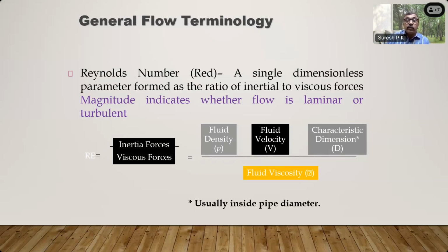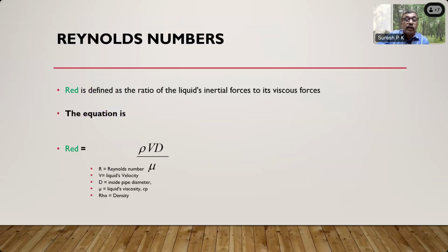So that is the Reynolds number. It uses the liquid's viscosity in centipoise. So this is the indication which you normally get. These are the terms you generally encounter with the Reynolds number, along with uncertainty, accuracy and repeatability, when you are dealing with a flow meter.